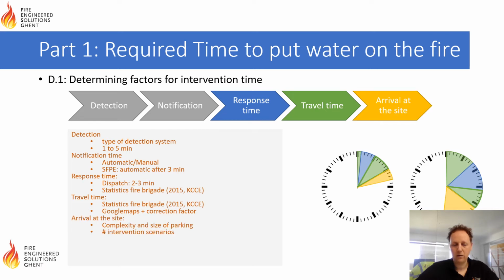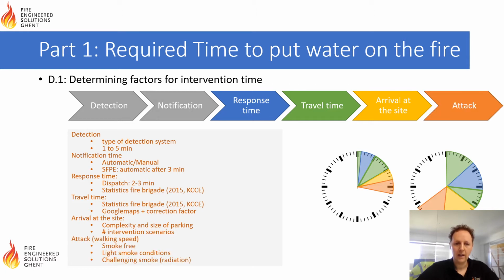After that, you have the time required to set up the equipment, arrival at the site, looking at the intervention scenario, where to enter the building, etc. And then lastly, you have the attack, or walking down the staircases, walking in certain zones that are smoke-free, light smoke, or challenging smoke where radiation plays a role. So looking at the timeline, we see that in the best case, we would be looking at something around 15 minutes, and in the not worst case, but realistic case, would be around 40 minutes, would be exceptional.